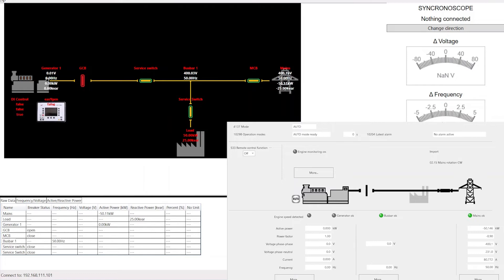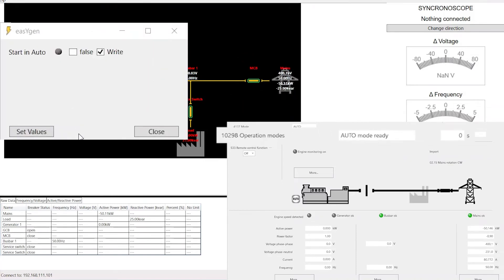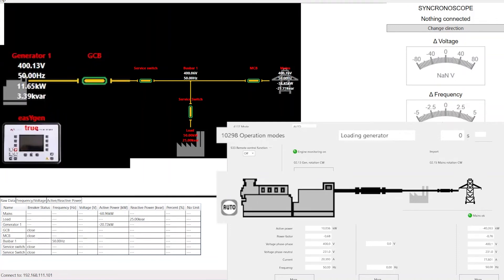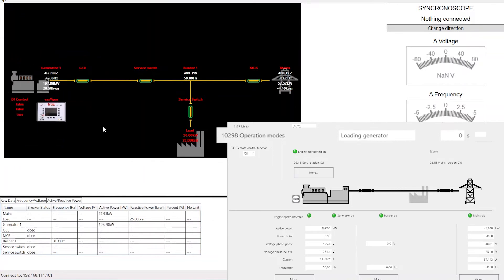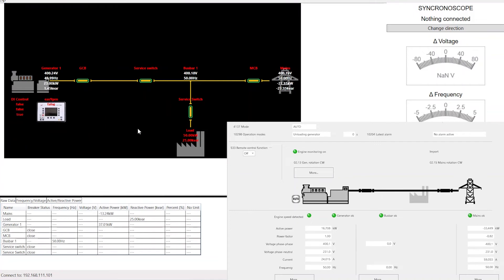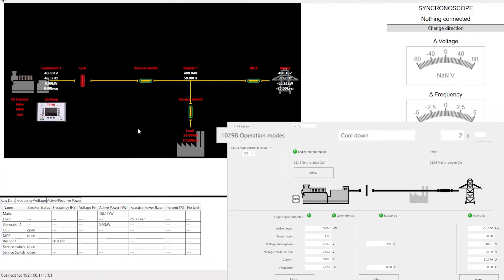Let's see how breaker mode parallel is working. As you can see, the load is supplied by the mains incomer. When the genset receives a start command, the engine starts up and the generator ramps up to its rated values. When rated values are reached and monitoring is activated, synchronization is started. When bus bar values and generator values are synchronized, the EasyGen closes the GCB and ramps the generator to the active power set point. Now the load is supplied by mains and genset. When the start request is removed, the generator unloads the GCB and opens it when the unloading limit is reached. Now the application is fed by mains only again and the genset is running in cooldown sequence. After the cooldown, the engine is stopped.